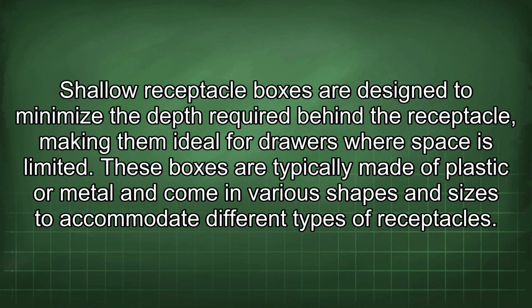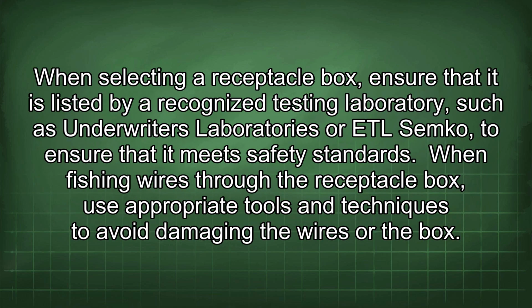It is essential to consider the specific type of receptacle box suitable for drawer installations. Shallow receptacle boxes are designed to minimize the depth required behind the receptacle, making them ideal for drawers where space is limited. These boxes are typically made of plastic or metal and come in various shapes and sizes to accommodate different types of receptacles. When selecting a receptacle box, ensure that it is listed by a recognized testing laboratory such as Underwriters Laboratories or ETL Semko to ensure that it meets safety standards.